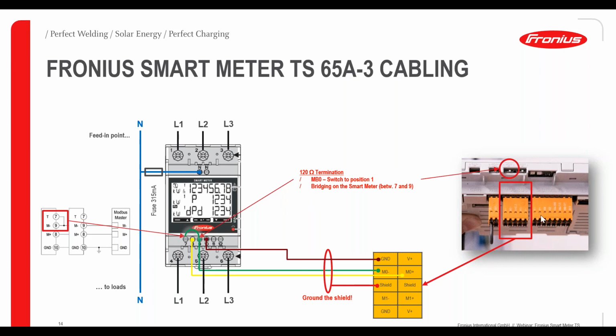And on the data communication card of the inverter, you see this tiny little switch here. You just switch it to position 1, and that way you have activated the termination. One other important thing when it comes to the installation, which is not listed here, is that we use a twisted pair cable between data minus and data plus.